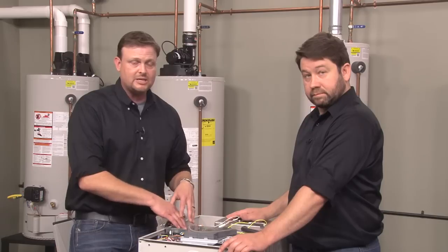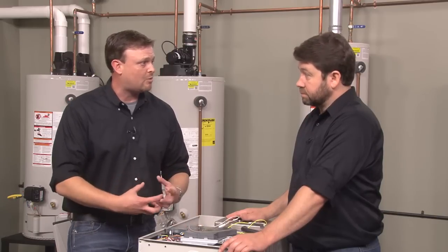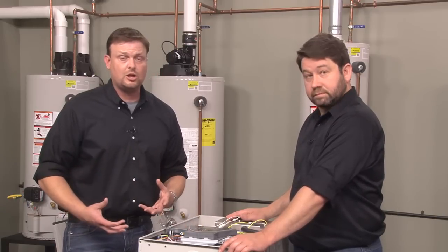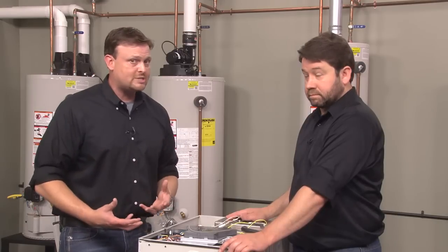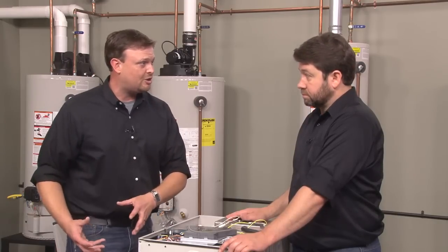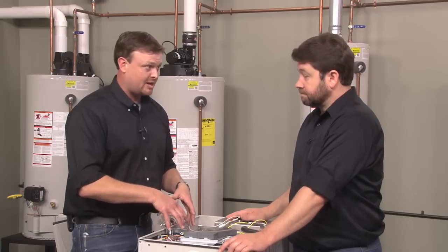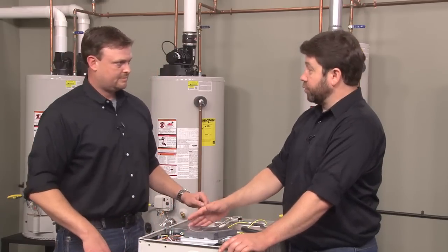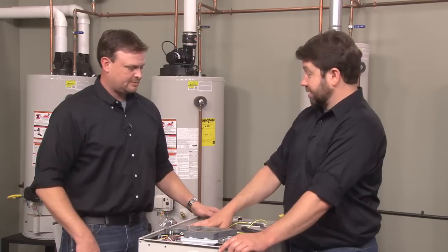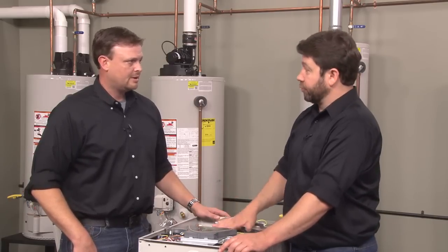It's got a bypass in there that allows cold water to mix with the hot water, and we want that bypass closed, because if you don't close it, when you delime the unit, all you're doing is deliming the bypass. We're just going to pump up and through the bypass and back out, because that's the path of least resistance. We're not pumping through the actual heat exchanger.